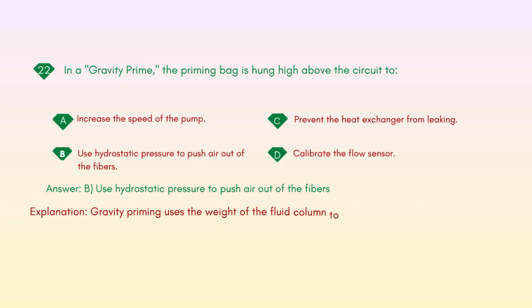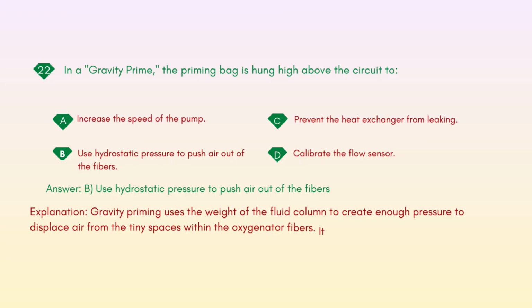Explanation: gravity priming uses the weight of the fluid column to create enough pressure to displace air from the tiny spaces within the oxygenator fibers. It is often a slower, more controlled method than using the pump to prime.